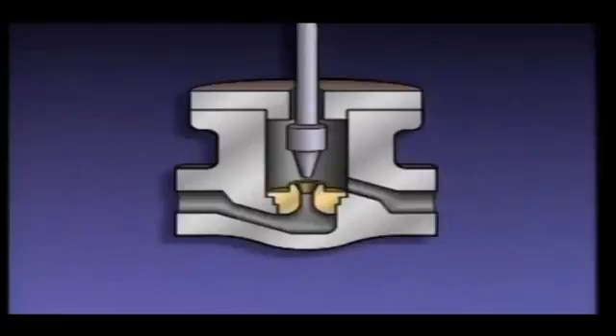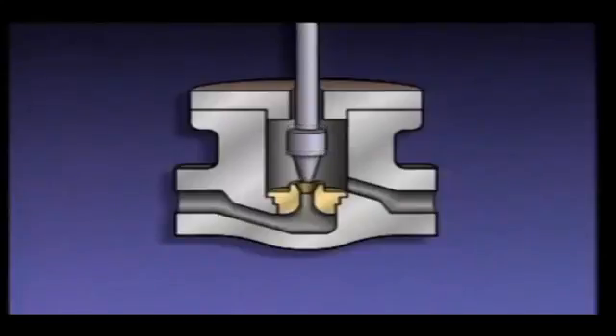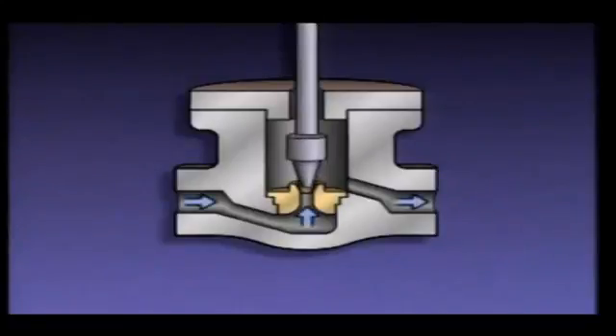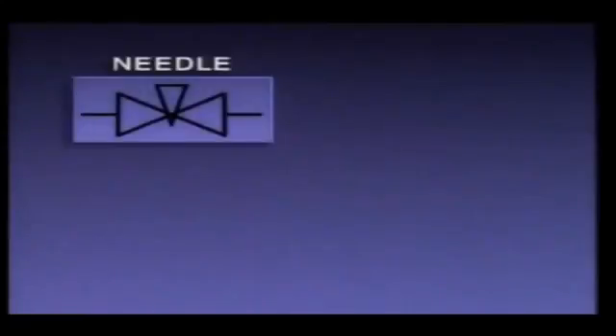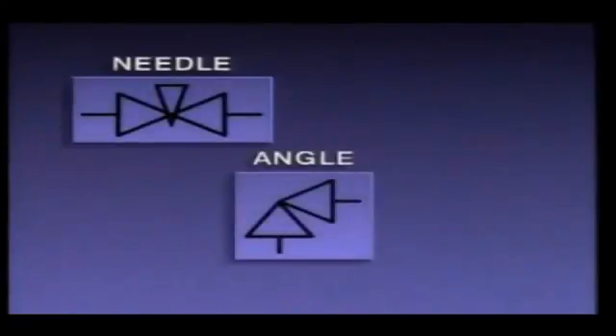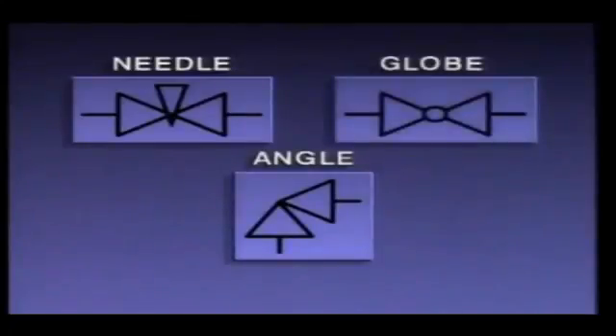A needle valve has basically the same parts as other globe valves, but its disc is shaped like a needle. The needle extends deep into the seating area of the valve. A small movement of the stem causes a small gradual change in the flow rate through the valve, giving the needle valve an extremely fine throttling ability. On a piping system diagram, a needle valve generally looks like this, an angle valve generally looks like this, and a globe valve generally looks like this.